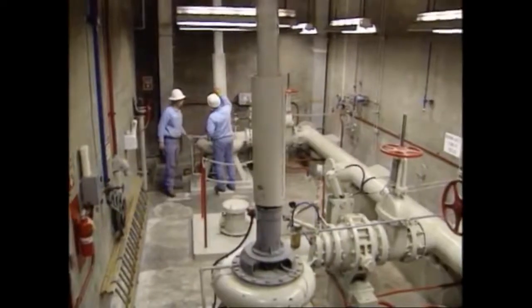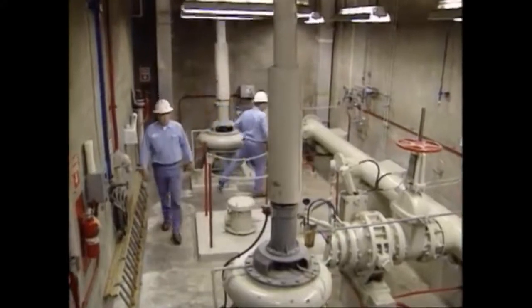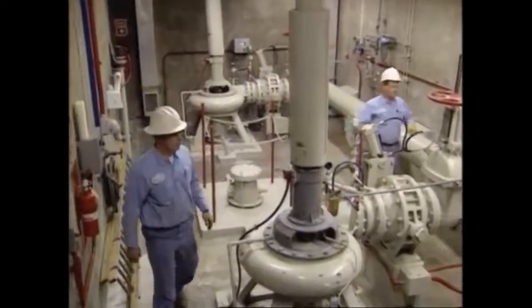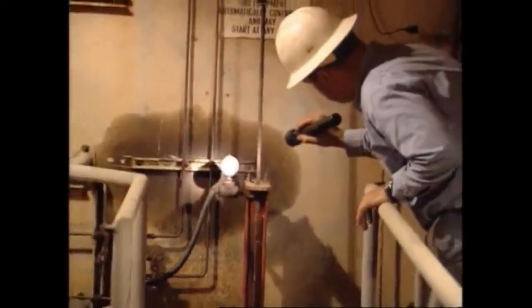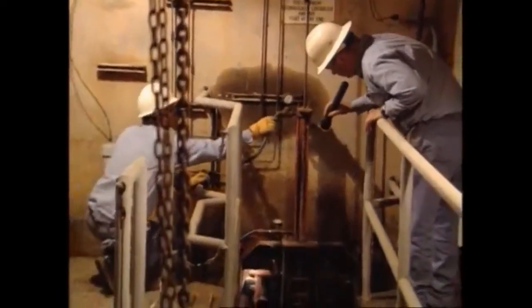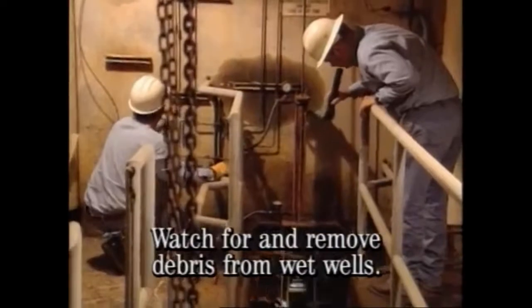Start the smallest pump first, and start pumps in order of increasing capacity. If a pump with a large capacity is started first, the wet well level may fall quickly, and by the time the crew is ready to test run the last pump, the wet well level is too low for automatic operation of the pump. The pump may be inspected in the manual mode of operation, but this does not guarantee that it will operate in the automatic sequence.